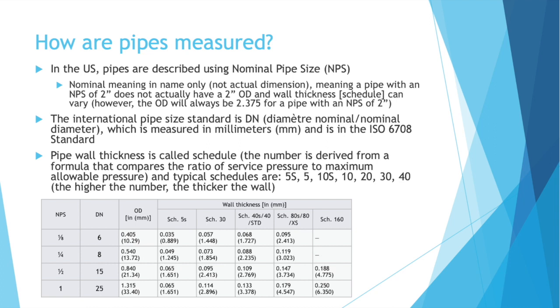Pipe wall thickness is called schedule, and that number is derived from a formula that compares the ratio of service pressure — when the pipe is normally in service — to maximum allowable pressure, a pressure that shouldn't be exceeded in the pipe. Common schedules are 5, 10, 20, 30, 40, and 80. Schedule 40 seems to be the standard that you order for pipe unless you specify otherwise.